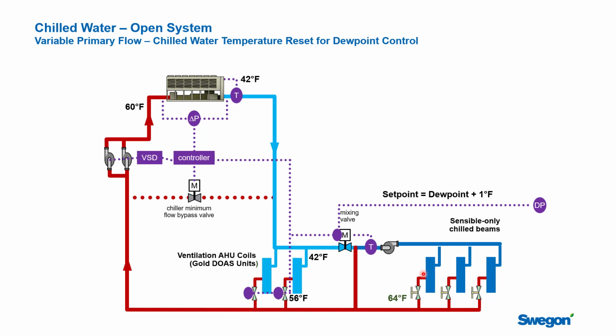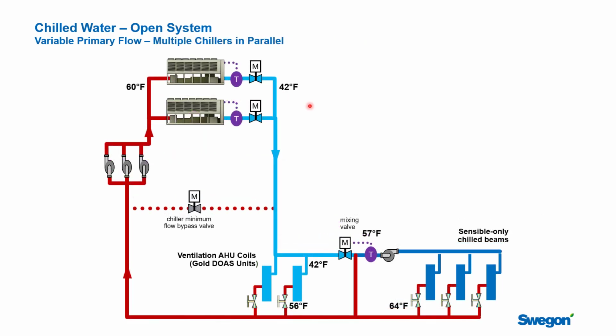And if you start to see high dew point anywhere on the area that's serviced by this chilled beam loop, then you could start to reset the temperature in that space to avoid a condensation issue and having to close the valves off entirely. I spent a lot of time talking about how you would size the chillers in the chiller plant or how many chillers you would have. Most chilled beam projects are large enough that you're going to have multiple chillers, and that those chillers would typically be put in parallel arrangement like you're seeing here.